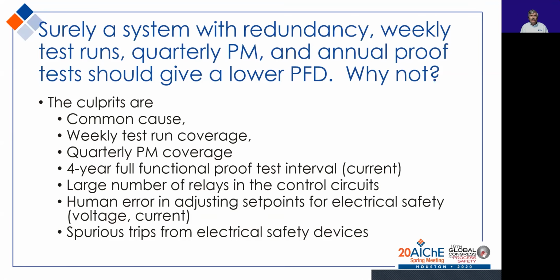Surely a system with redundancy, weekly test runs, quarterly PM, and annual proof tests should give a lower probability of failure on demand. Why not? Well, the culprits are common cause, the weekly test run coverage, the quarterly PM coverage, the 4-year full functional test that we do at that frequency currently, the large number of relays in the control circuit, human error in adjusting set points for electrical safety, such as voltage, current, and spurious trips from the electrical safety devices.